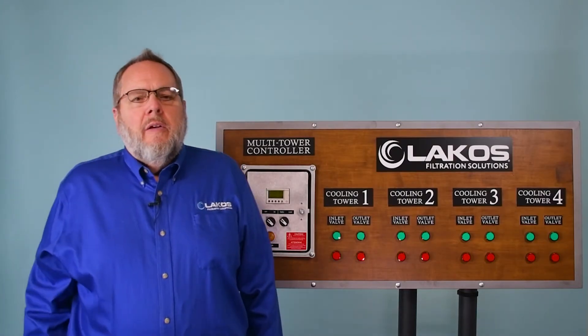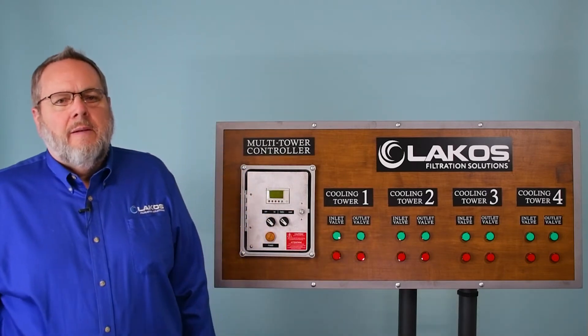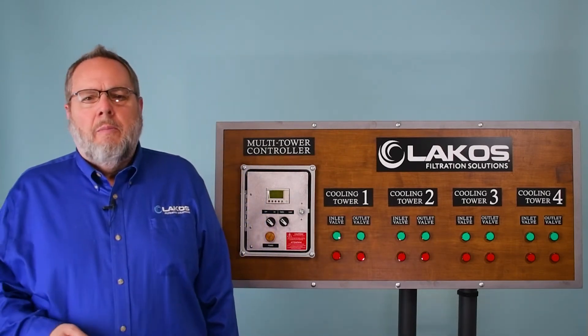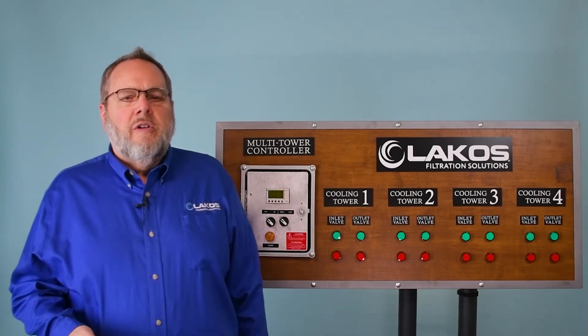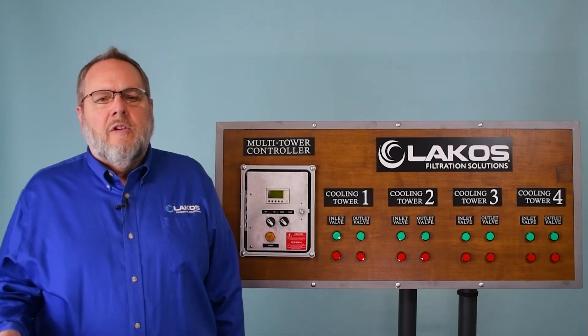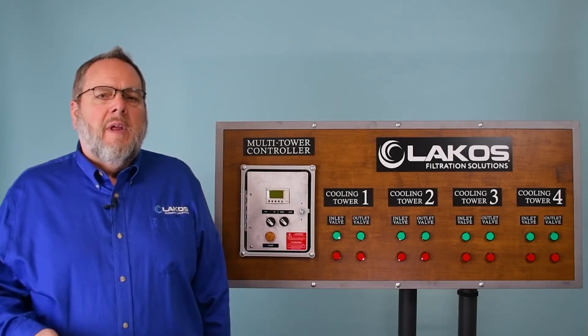Do you have to do anything different with your setup when using the multi-tower switching kit? The answer is no. You would follow the same parameters that LAKOS already recommends for installing a sweeper piping system. Your LAKOS filtration package would still need to be located within 20 feet of the towers and piped per LAKOS recommendations for inlet and outlet piping. In most cases, this would use a header design with branches going out from the header to each tower.